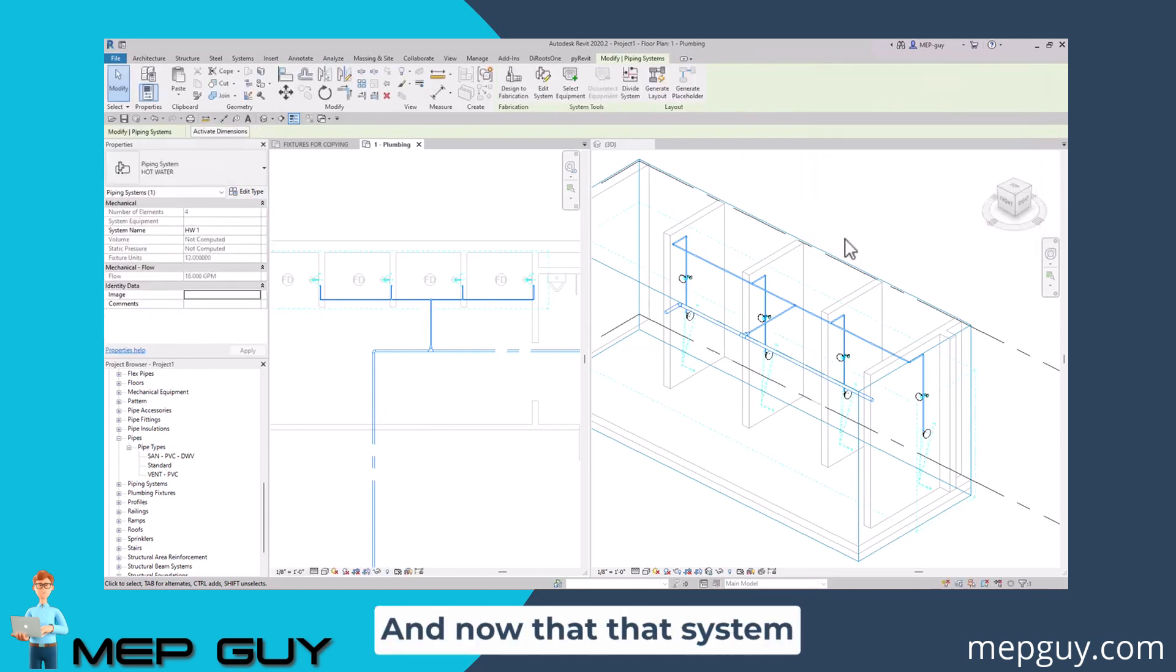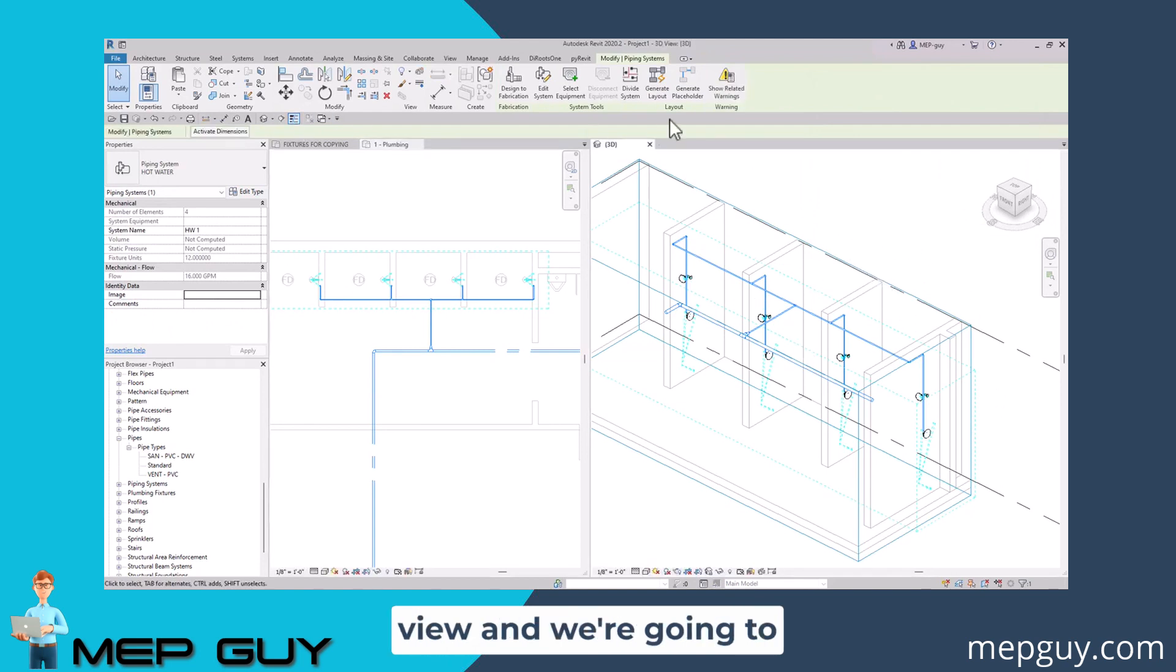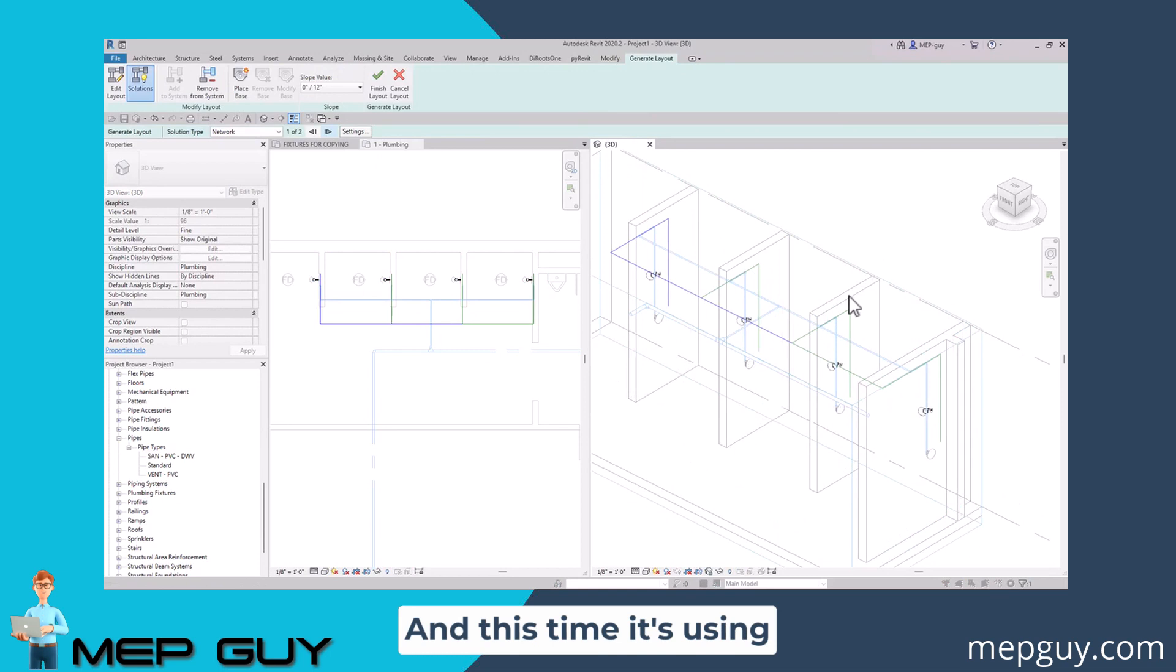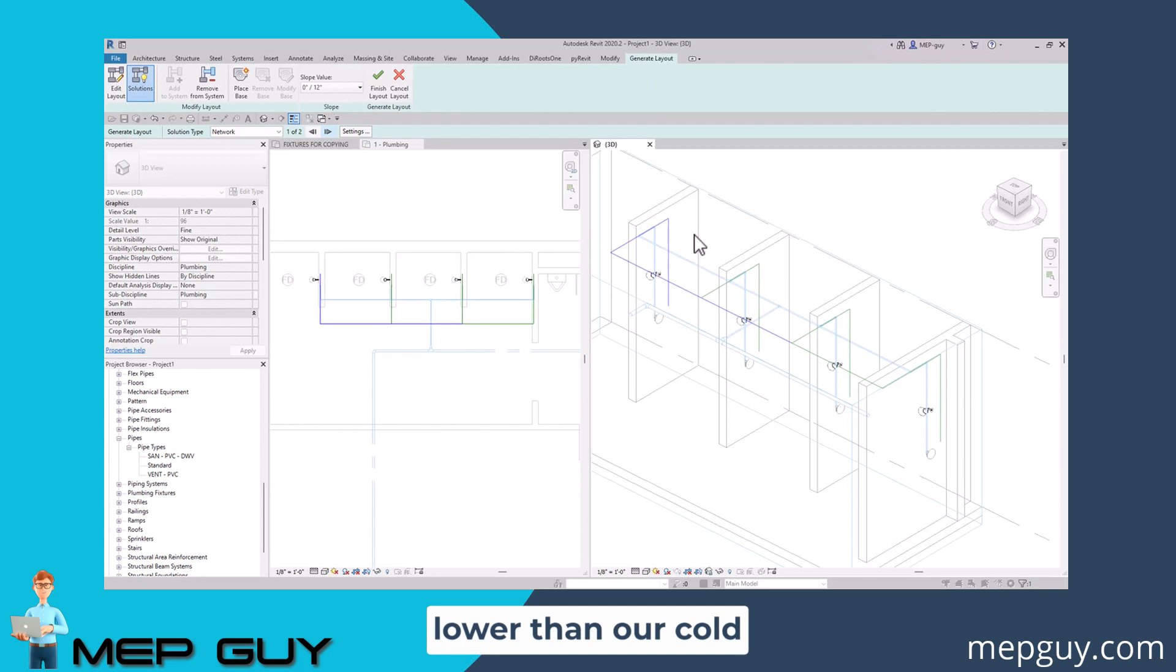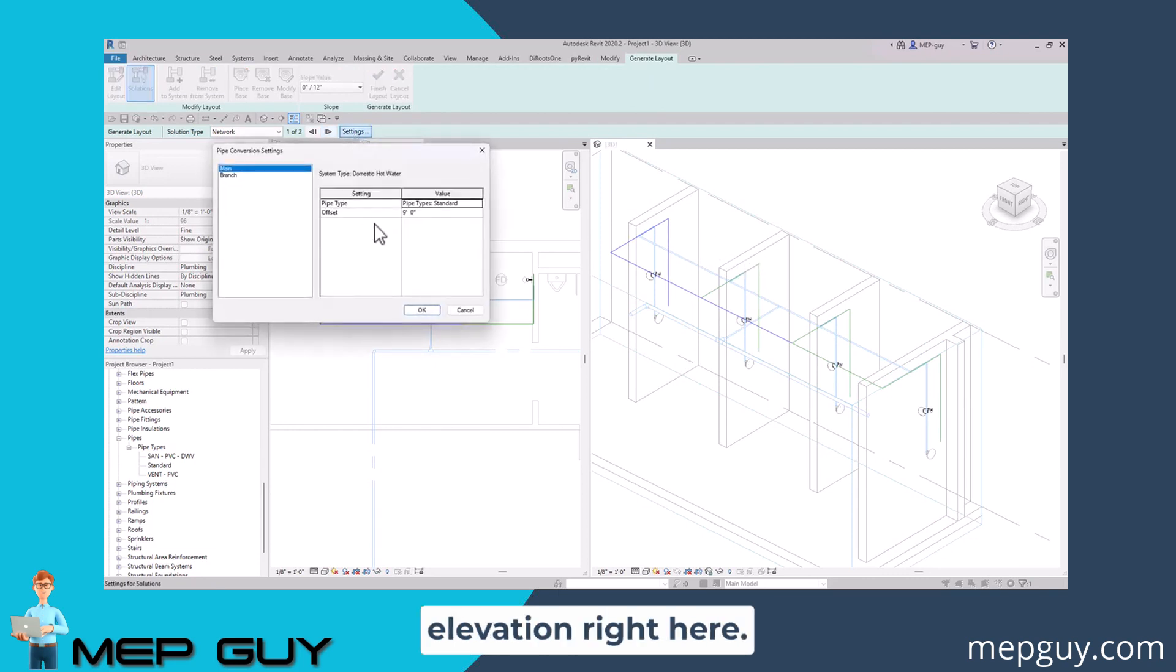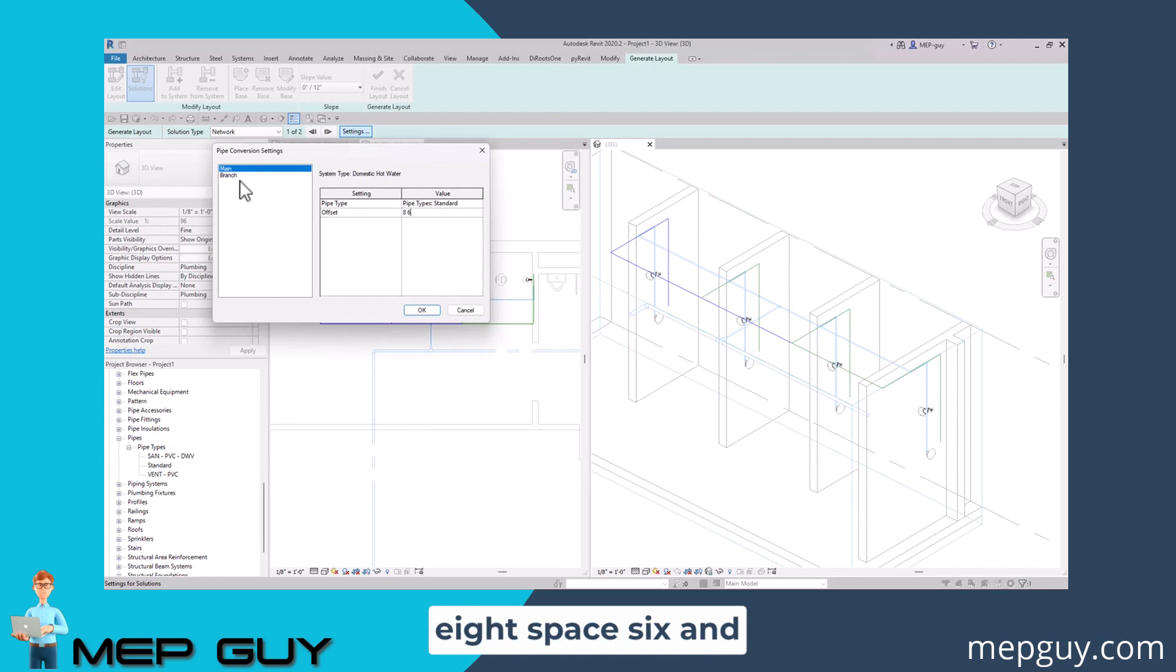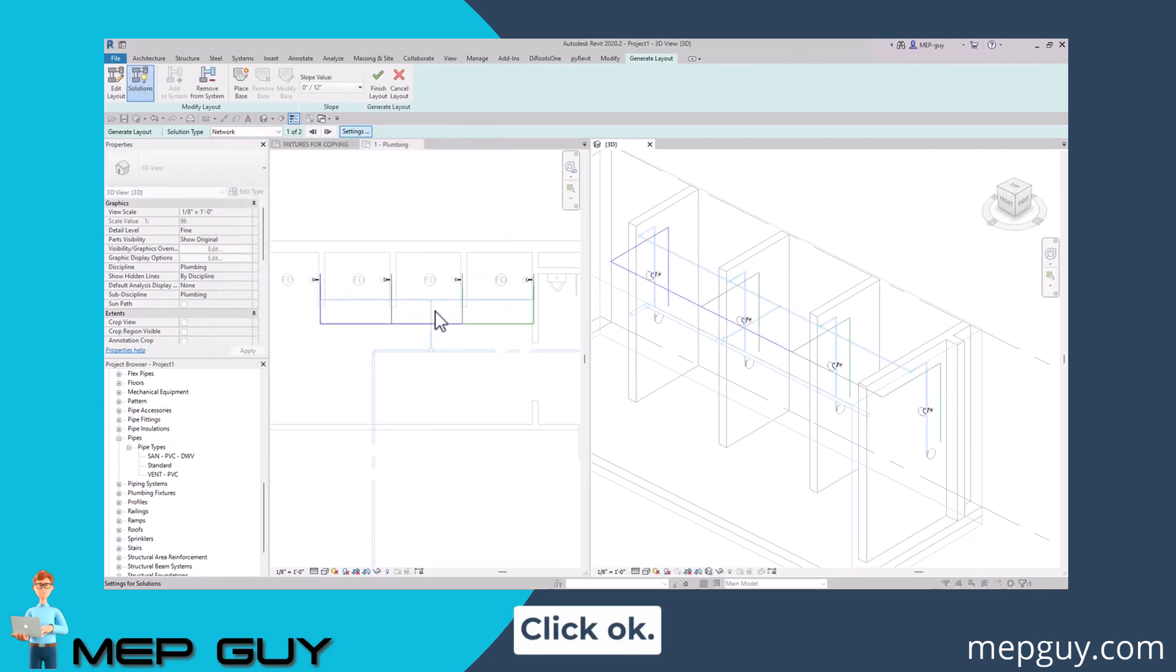Now that that system has been created, we'll click into our 3D view and generate another layout. This time it's using the hot water system. Maybe we want the hot water to be a little lower than our cold water system. We can set the elevation right here. I'll temporarily set that to eight foot six, using eight space six. We'll do the same thing for the branch, eight space six, then click okay.